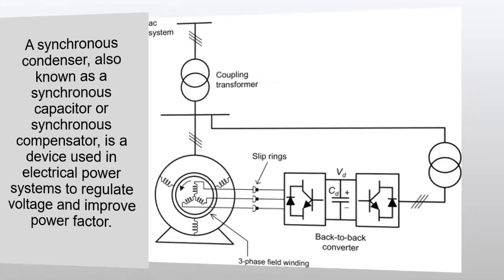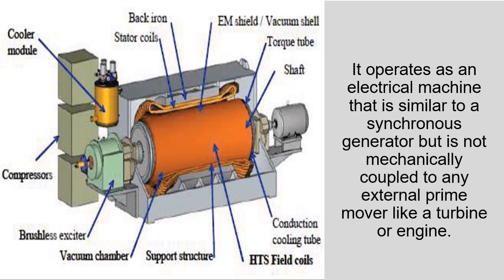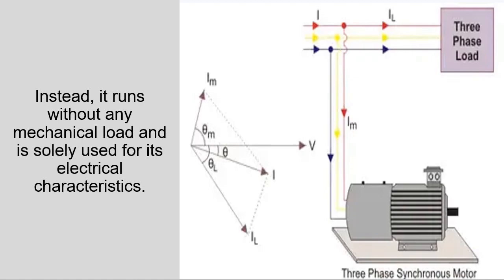is a device used in electrical power systems to regulate voltage and improve power factor. It operates as an electrical machine that is similar to a synchronous generator but is not mechanically coupled to any external prime mover like a turbine or engine. Instead, it runs without any mechanical load and is solely used for its electrical characteristics.